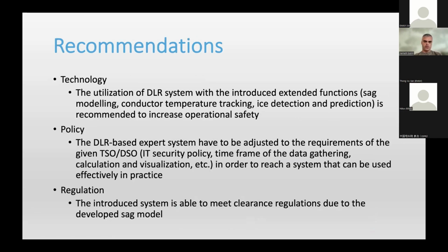So finally, just a short conclusion. What is the recommendation based on our work package inside of the FLEXITRANSTORE project? From the technology point of view, the utilization of the DLR system with the introduced extended functions like the sag modeling, conductor temperature tracking, ice detection, and prediction is recommended to increase the operational safety for both the TSO and the DSO level. The DLR-based expert system has to be adjusted to the requirements of the given TSO and DSO, meaning IT security policy, time frame of the data gathering, calculation and visualization, and so on, in order to reach a system that can be used effectively in practice.